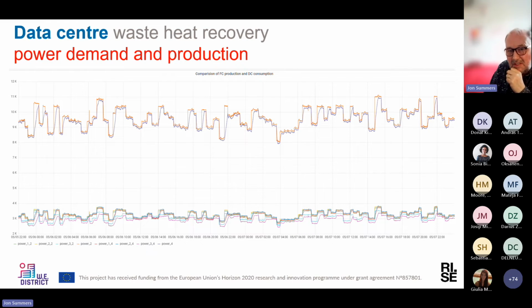So here you can see one where the power is immediately gone from around about the requirements of power, because the workload on the data center has gone from around about 8.5 kilowatts up to 11 kilowatts. And the slightly purple line is trying to catch up. So this is what is actually being produced by the fuel cells. And sometimes, when the power draw drops down, you can't see it so much here because it's a little bit too fine, but the fuel cells are overproducing. So when we're ramping up the power demand, the fuel cells are underproducing, and when we're dropping down the power demand, the fuel cells are overproducing.